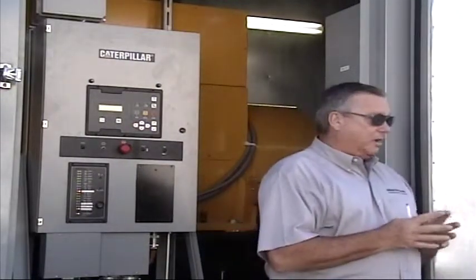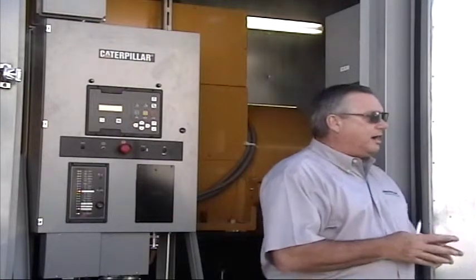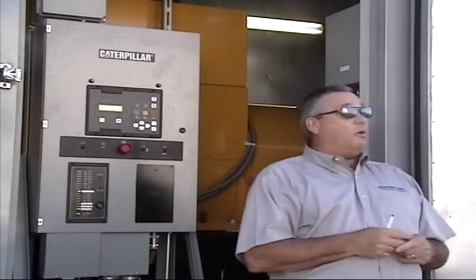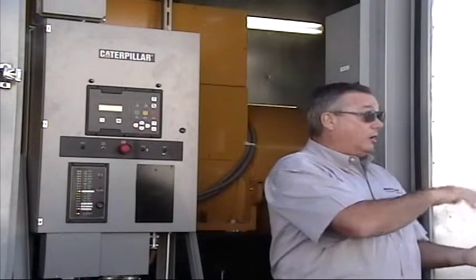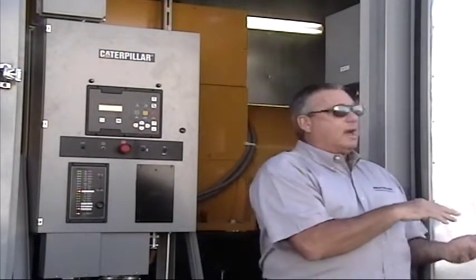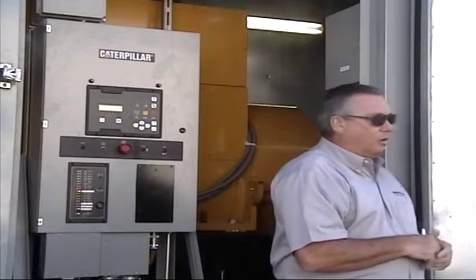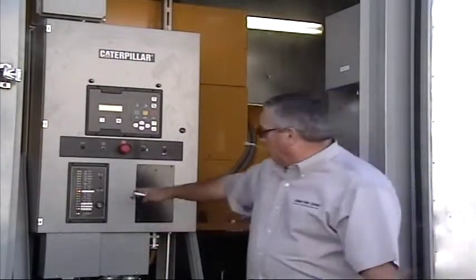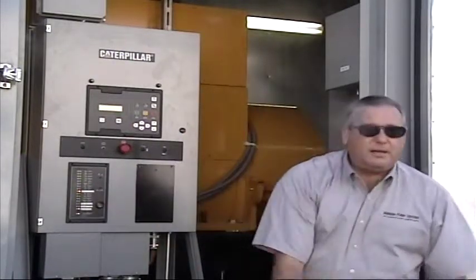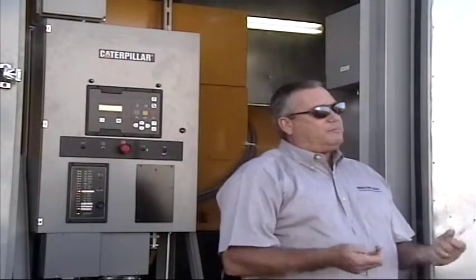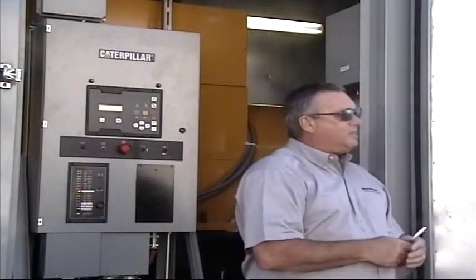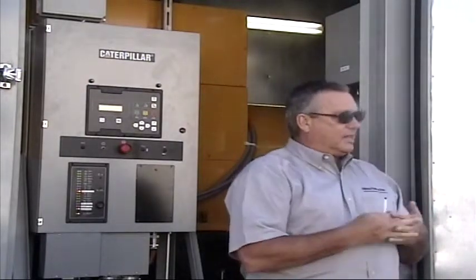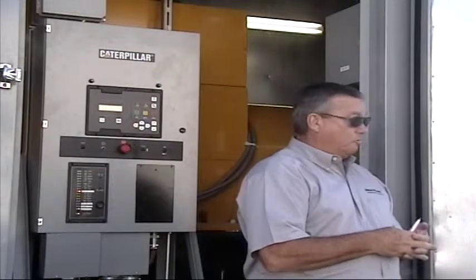Also, low oil pressure. Obviously we never want to see it, but a bottom end failure would cause that, and obviously an oil pump failure, or you could have actual low oil in the sump that would not allow you to have full pressure, and that might give you a low oil pressure shutdown. And then overspeed: you get about a 10% overspeed on it, past 1800. If it continues to rise, we've lost governor control. It'll continue to go up until it hits that threshold, and it'll shut down for overspeed.